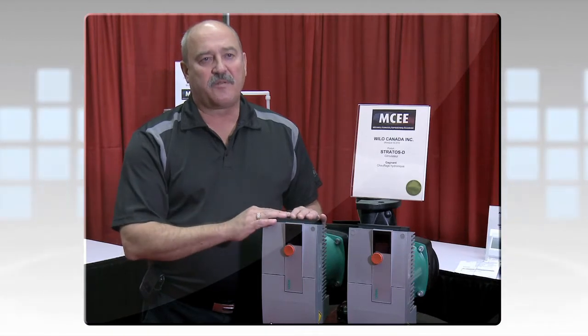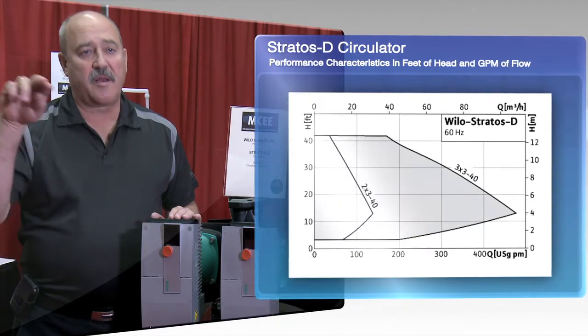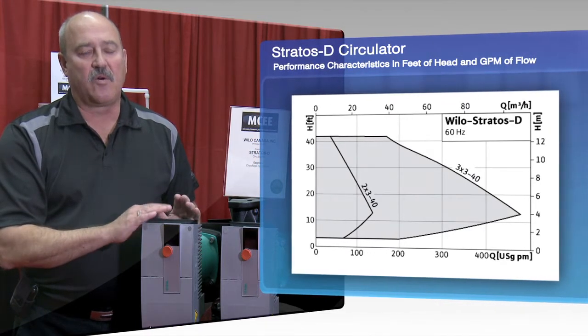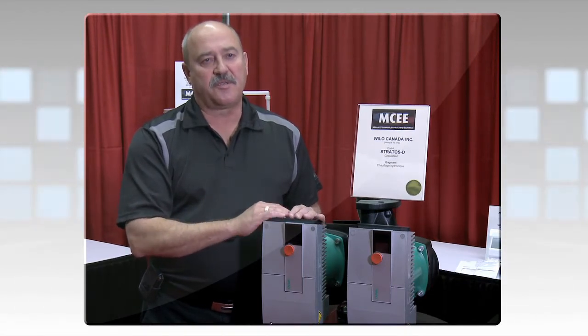The other operating mode is variable differential pressure, delta p-v. In that mode, the pump curve is actually an inclining curve, so it matches the friction loss of the system. It only gives you as much flow and as much head as you need to overcome the friction loss in the system. That's when you achieve your highest energy efficiencies.